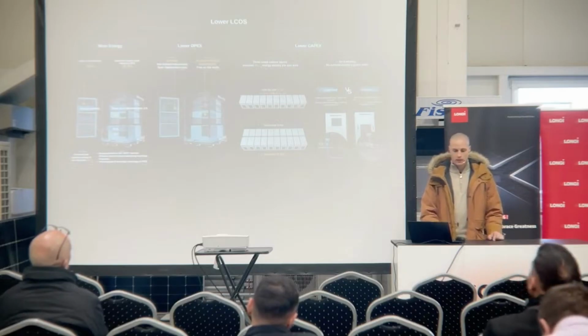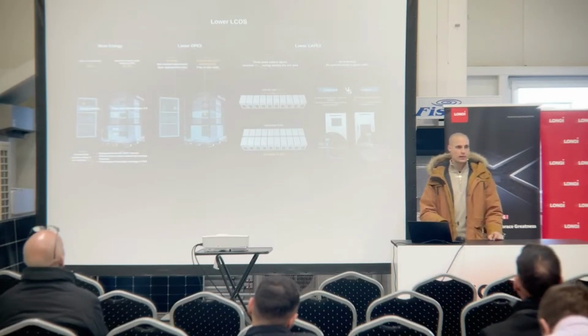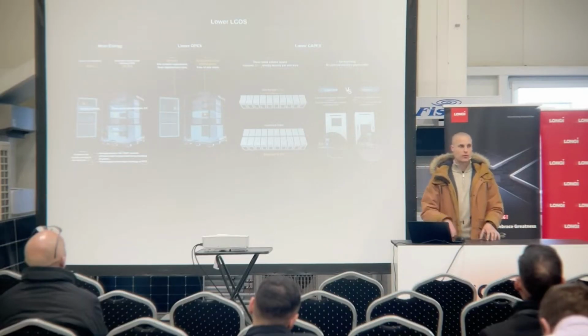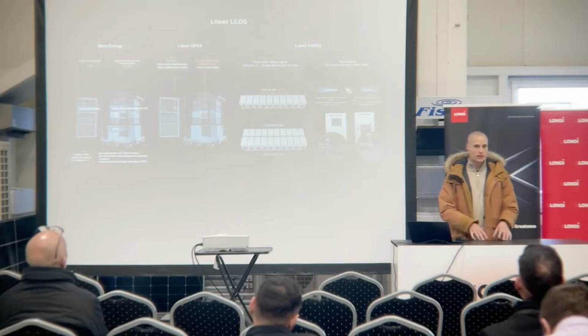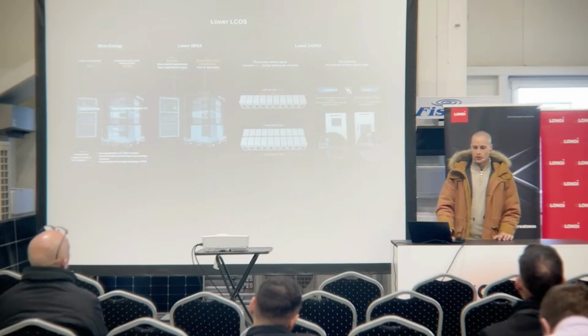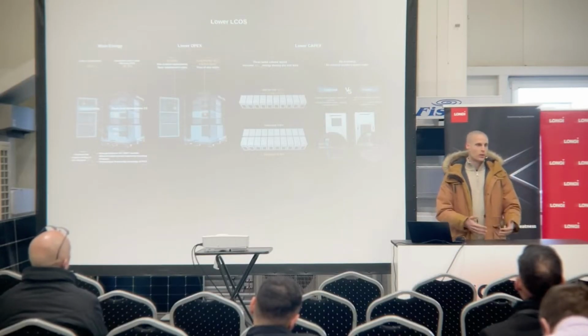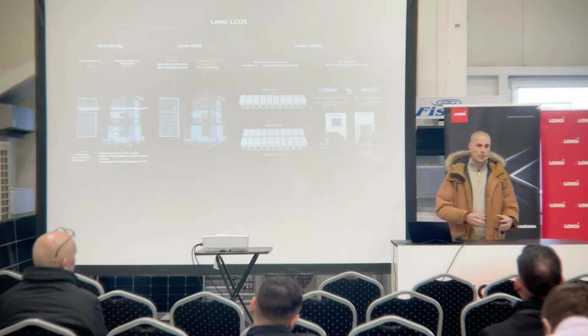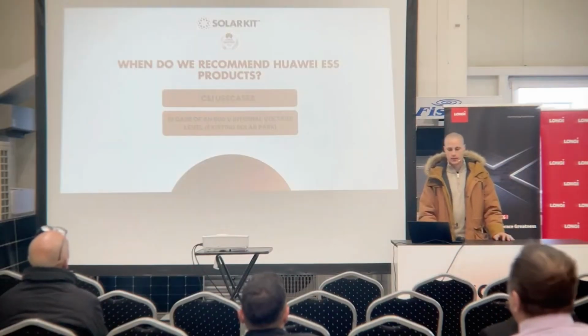One thing to mention here is that since they are all pre-built and weigh almost 3 tons, you need something on site that can handle the 3 tons. Previously, since it wasn't assembled and you had to do it on site, the cabinet was roughly 1 ton, so you just needed to lift that 1 ton and move it, and then the battery packs were roughly 160 kilos. Compared to that, now we have one cabinet that's almost 3 tons, so you have to keep in mind that you somehow have to operate that 3 tons all around the working place.